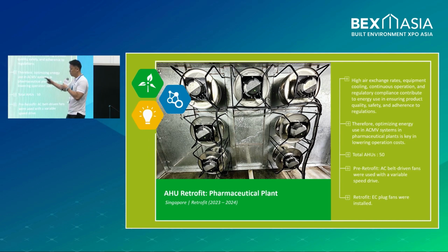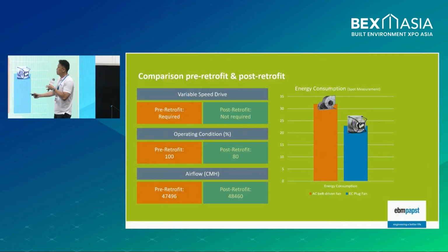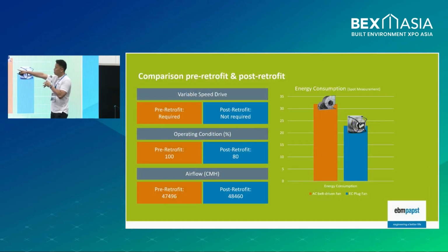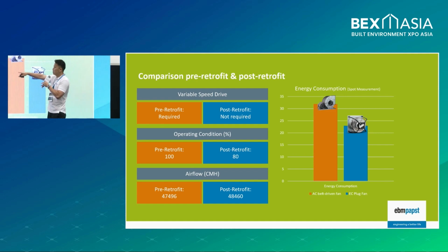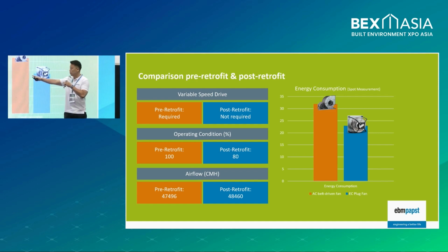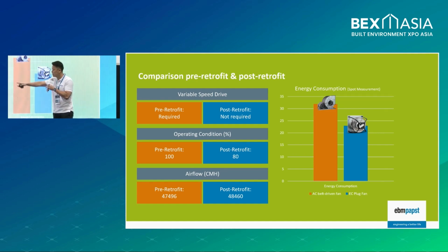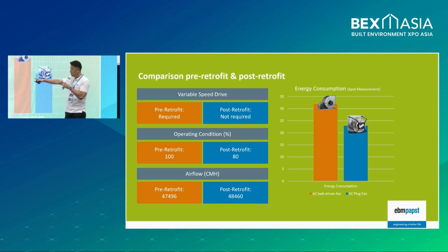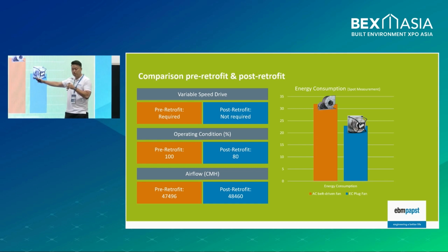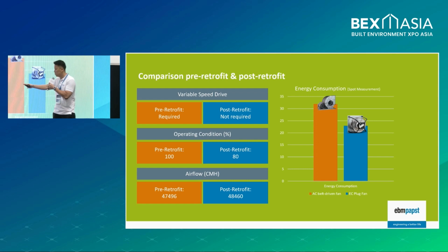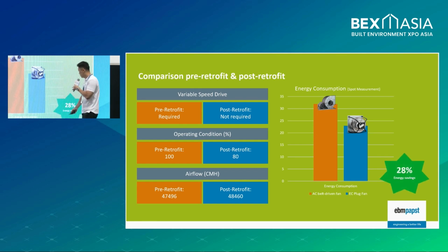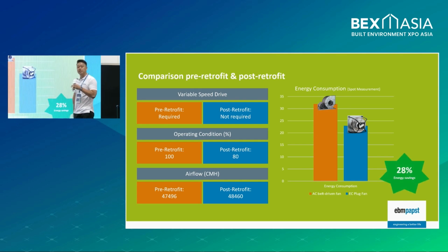Subsequently, we will retrofit another 50 AHUs. Before retrofit, they needed a VFD. After retrofit, we don't need a VFD anymore. Operating condition goes from 100% to 80%, meaning we still have a buffer of 20%. So if one fan or even 2 fans break down, I think we can still achieve the airflow. Before and after retrofit, airflow is almost equivalent, and the energy saving is about 28 to 30%.